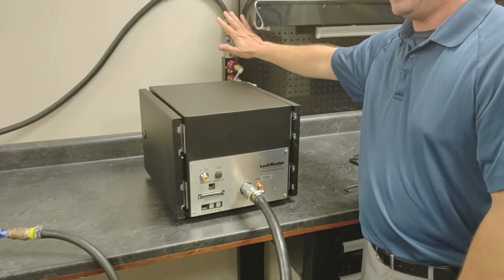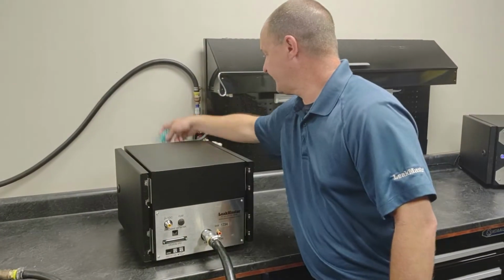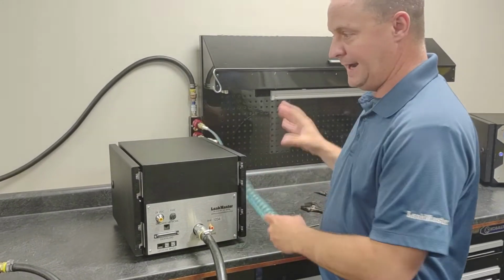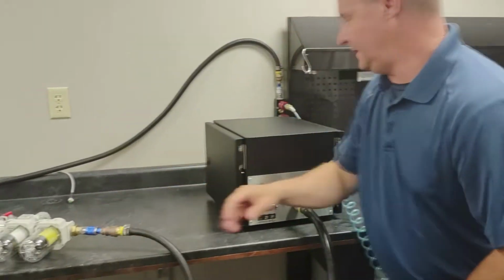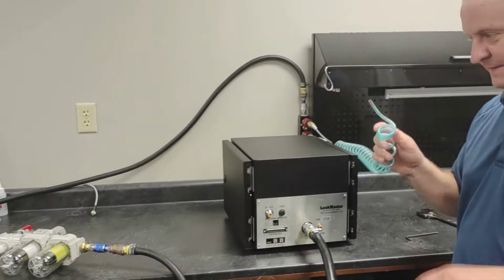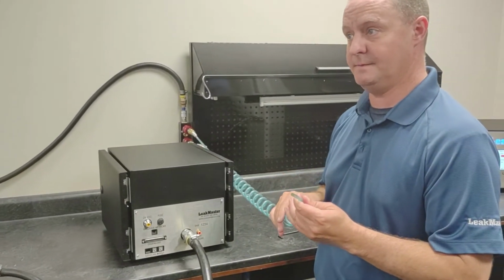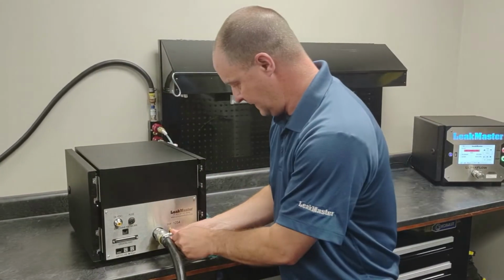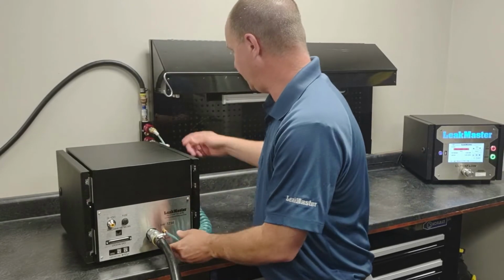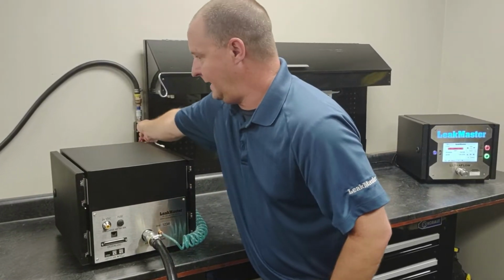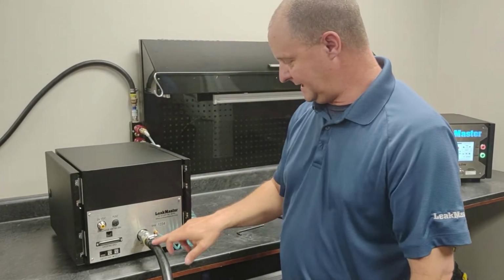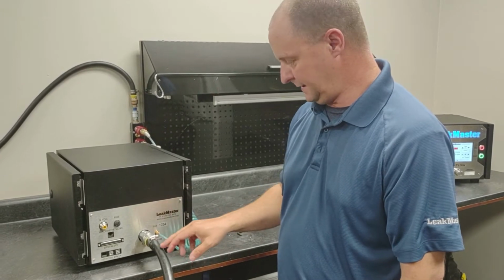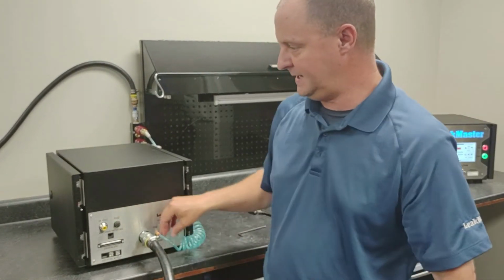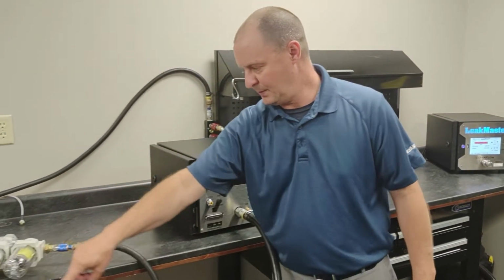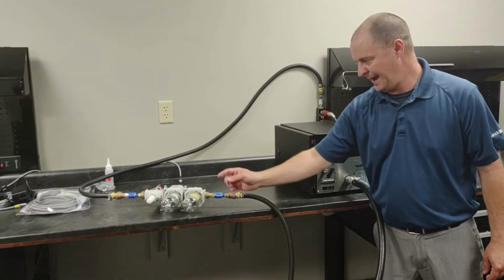Back here on my supply source, now keep in mind, I'm filtered. I already have one of these before this, so I've already filtered my air, and you still want to have clean, dry air coming in here. I'm going to supply my pilot pressure here, and it's important to keep this and this separate. You don't want to tee off right here. You want to tee off probably before your ballast tank.